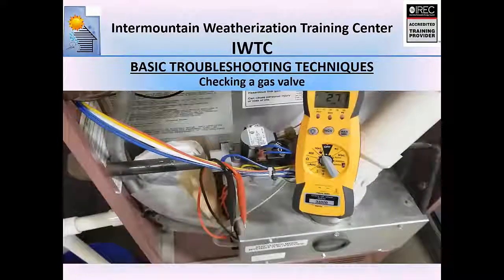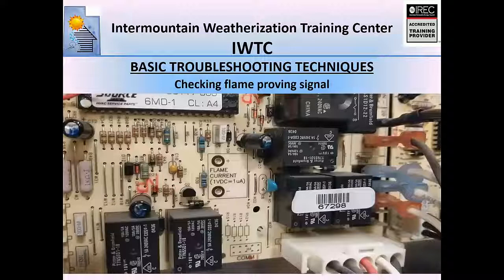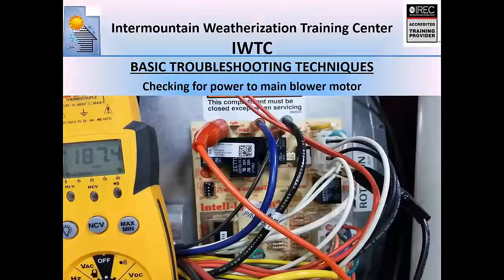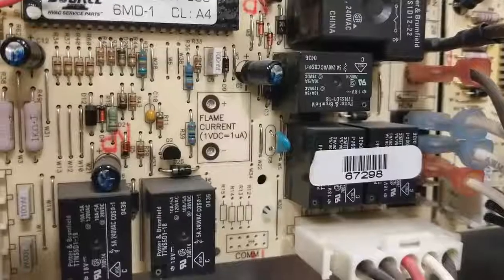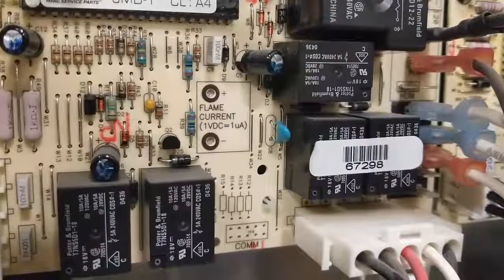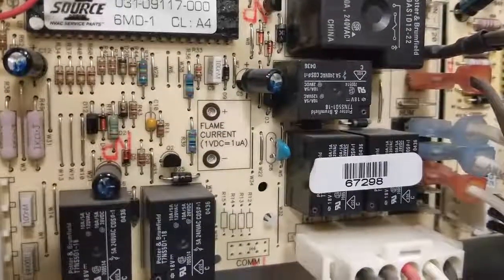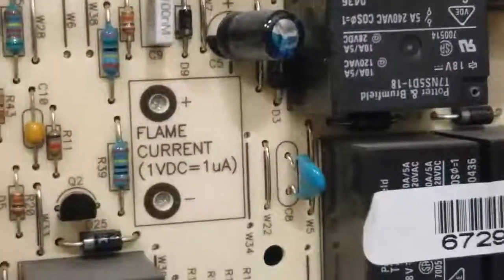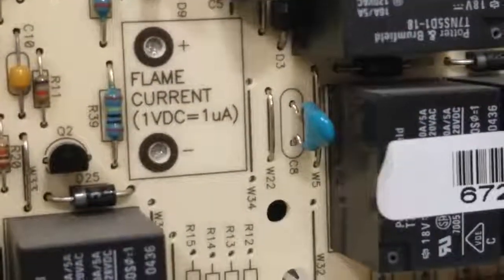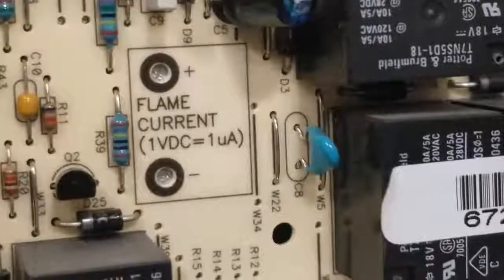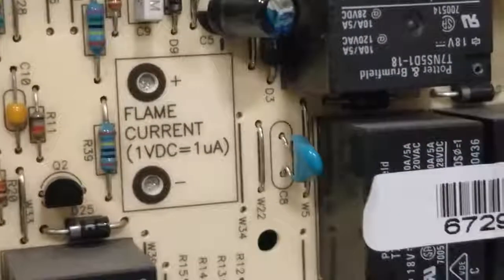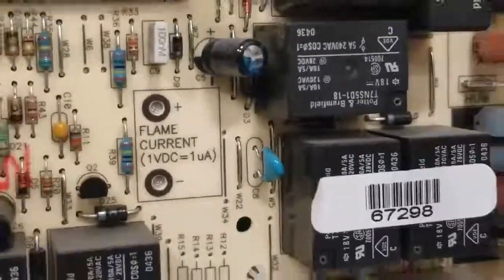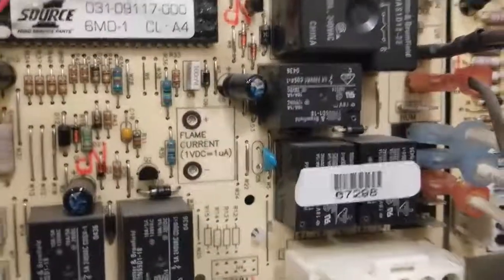All right. Next is checking for flame proving signal. So again, I've got a little video to take you through that. Real easy check. Okay, checking for flame rectification, or what we call flame sensing current, is another real easy check. If you're lucky, the furnace you're working on will have this convenient port that you can check flame current right there. But that's not always the case, so we're going to go ahead and do it the old school way.